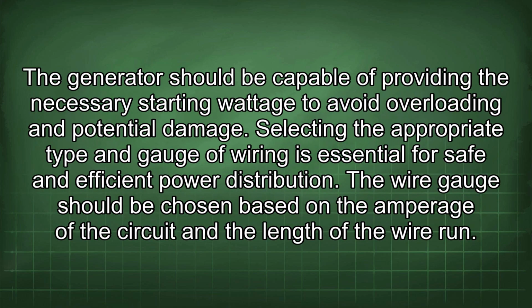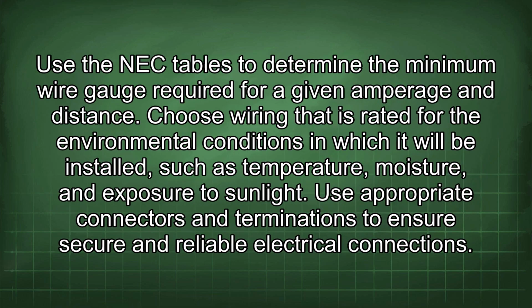The generator should be capable of providing the necessary starting wattage to avoid overloading and potential damage. Selecting the appropriate type and gauge of wiring is essential for safe and efficient power distribution. The wire gauge should be chosen based on the amperage of the circuit and the length of the wire run. Use the NEC tables to determine the minimum wire gauge required for a given amperage and distance.